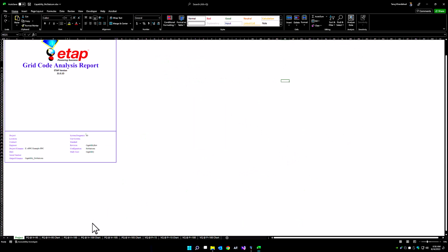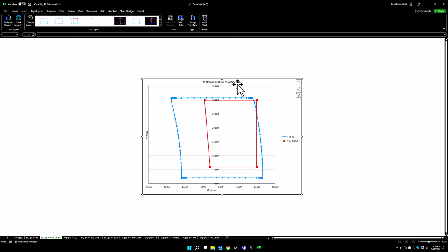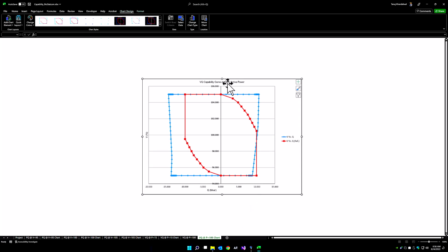Once the simulation is completed, we can essentially look at the grid code analysis report and look at the chart for PQ capability at 95% voltage. And we can see that the reference PQ curve is overstepping the PQ capability that's computed for this particular facility. So this region where there is intersection or overlap is where we have non-compliance. Similarly, we can see the same PQ capability at 100% voltage as well as 105% voltage, and the VQ capability at 100% active power. And again, we can see that there is a non-compliance region in the bottom right corner. This is without a STATCOM in place.